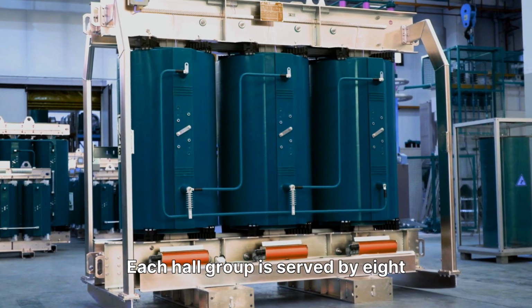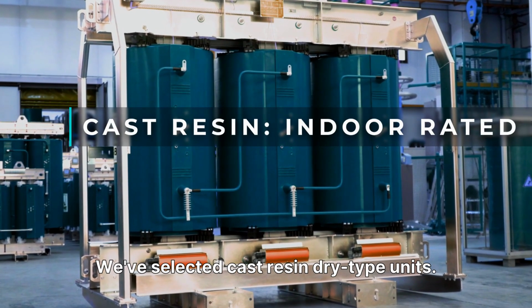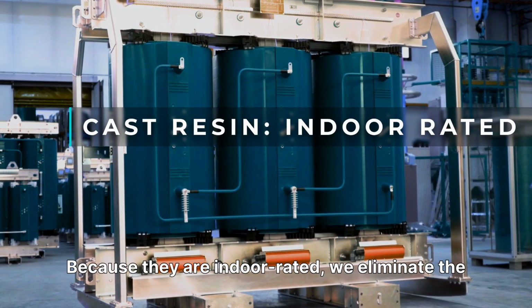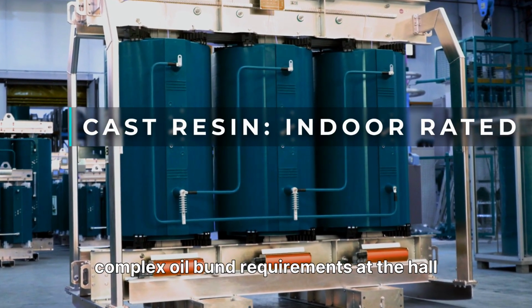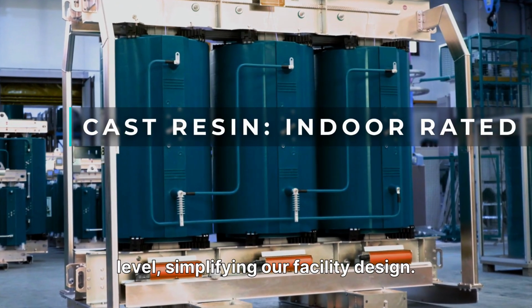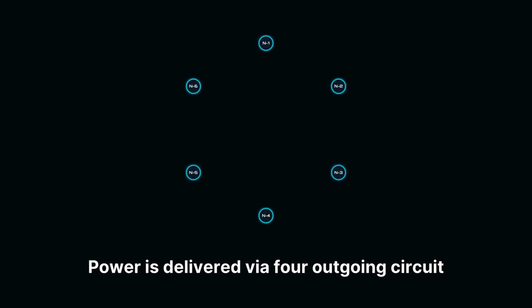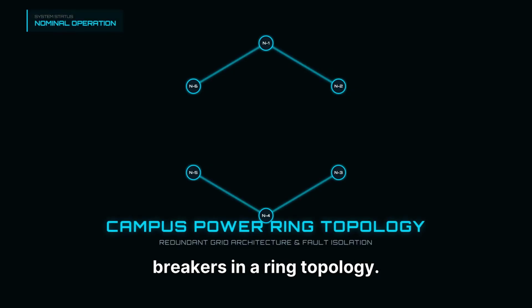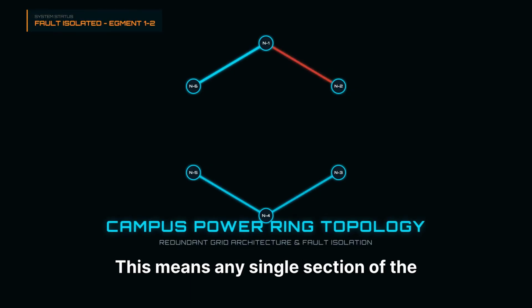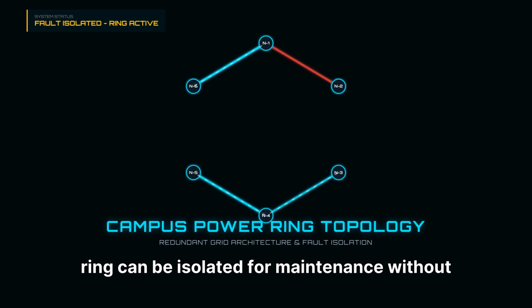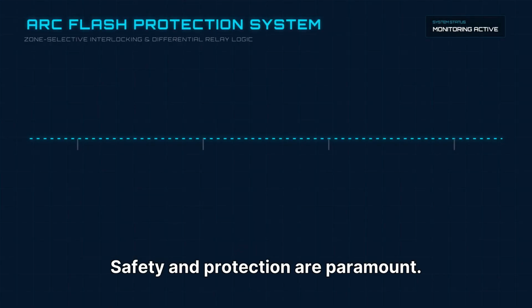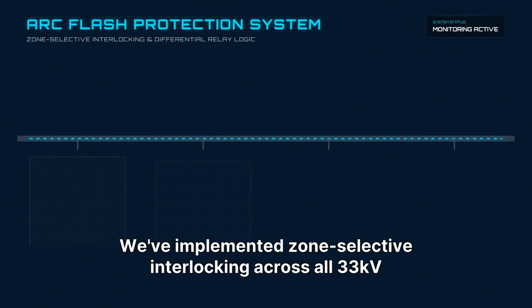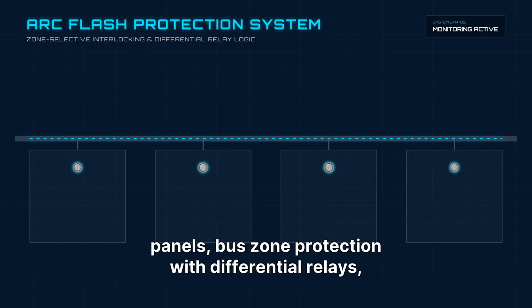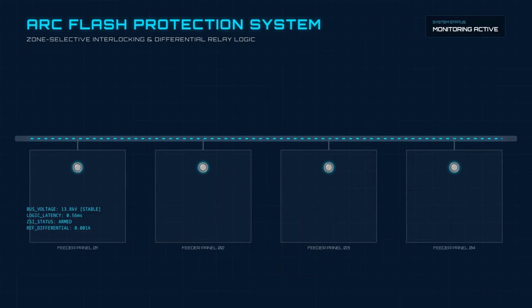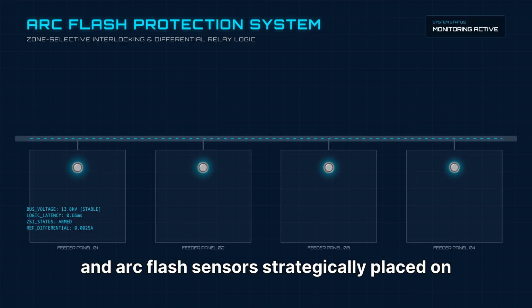Each hall group is served by 8 15 MVA transformers. We've selected cast resin dry type units. Because they are indoor rated, we eliminate the complex oil bund requirements at the hall level, simplifying our facility design. Power is delivered via 4 outgoing circuit breakers in a ring topology. This means any single section of the ring can be isolated for maintenance without loss of supply to any of the other data halls. Safety and protection are paramount. We've implemented zone-selective interlocking across all 33 kV panels, bus zone protection with differential relays and arc flash sensors strategically placed on all bus bars.